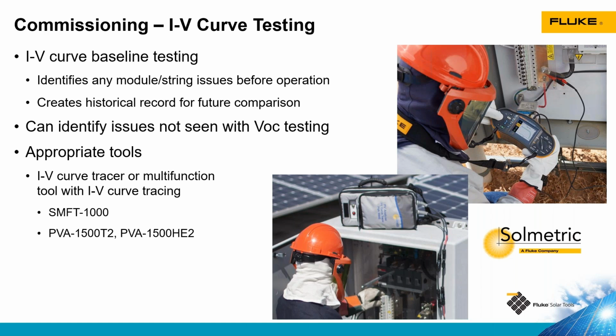Other tools like the PVA 1500 T2, when the efficiency exceeds 19%, their current rating goes from 30 amps down to 10 amps. The PVA 1500 HE2 is specifically designed for high efficiency modules. That's what the HE stands for. It will test any module of any efficiency up to its full 30 amp current rating.